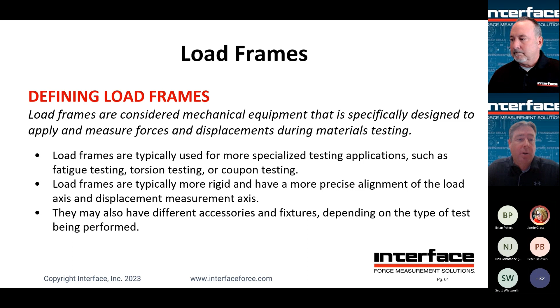Considerations for these types of tests: concentricity and test condition control typically allow for increased precision. So that's touching on that alignment again. We're able to much better control that alignment there. So hopefully the off-axis and extraneous loading conditions are mitigated there. Size to capacity for the maximum resolution. Again, since we can control the off-axis much better in most cases, we can size the capacity of the load cell much closer to the actual test range that you're working on.